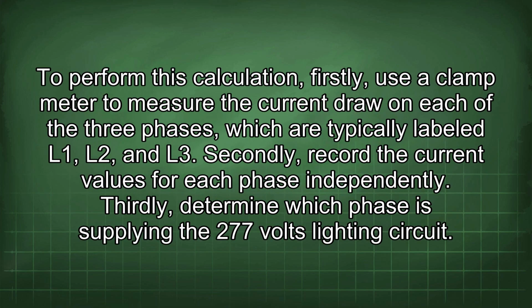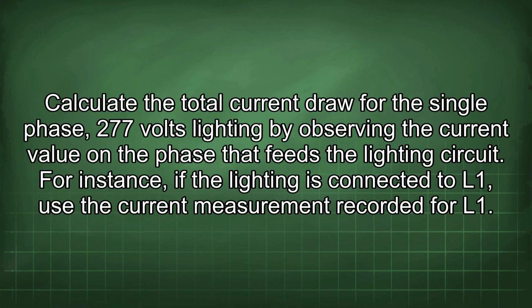To perform this calculation, firstly, use a clamp meter to measure the current draw on each of the three phases, which are typically labeled L1, L2, and L3. Secondly, record the current values for each phase independently. Thirdly, determine which phase is supplying the 277 volts lighting circuit. Calculate the total current draw for the single phase 277 volts lighting by observing the current value in the phase that feeds the lighting circuit. For instance, if the lighting is connected to L1, use the current measurement recorded for L1.